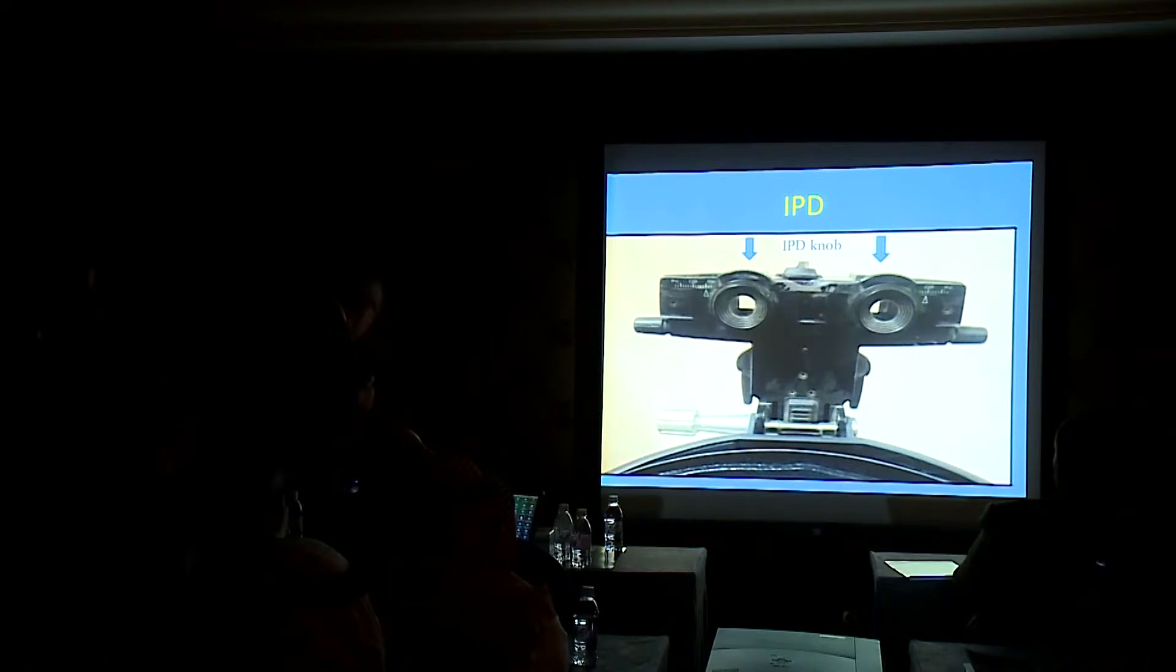Again, the interpupillary distance. You have to adjust it in front of both your pupils. Otherwise, you will get monocular field or monocular examination, and then you will not get the benefit you need from the indirect ophthalmoscope. You adjust the IPD by concentrating the light on your finger and trying to get a single image from both sides of the indirect.